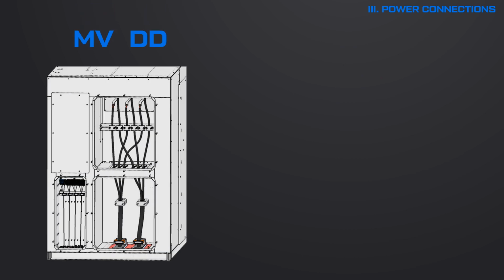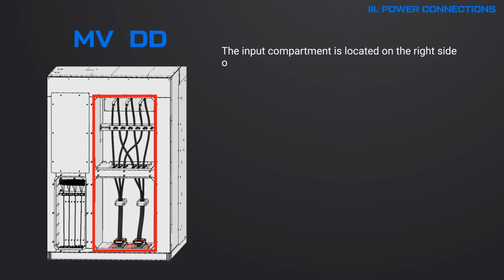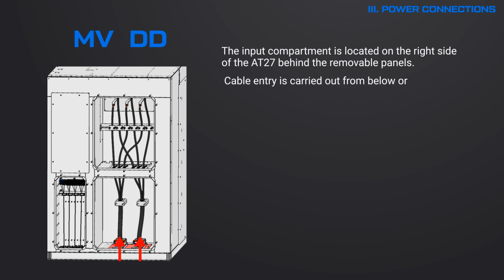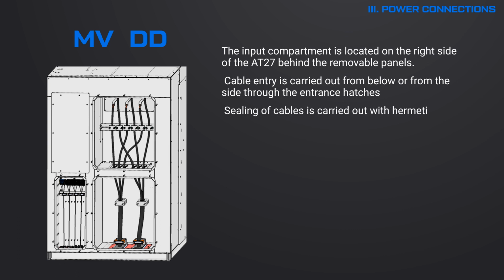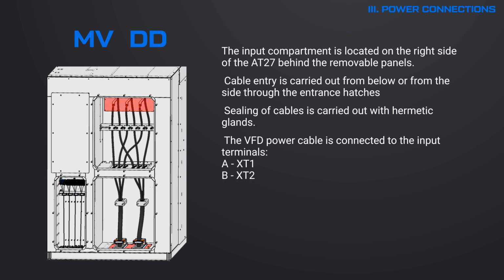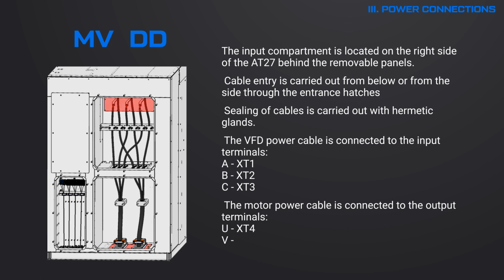The input compartments of the DD and MV line VFDs have a similar design. The input compartment is located on the right side of the AT27 behind the removable panels. Cable entry is carried out from below or from the side through the entrance hatches. Sealing of cables is carried out with hermetic glands. The VFD power cable is connected to the input terminals A, XT1, B, XT2, C, XT3. The motor power cable is connected to the output terminals U, XT4, V, XT5, W, XT6.